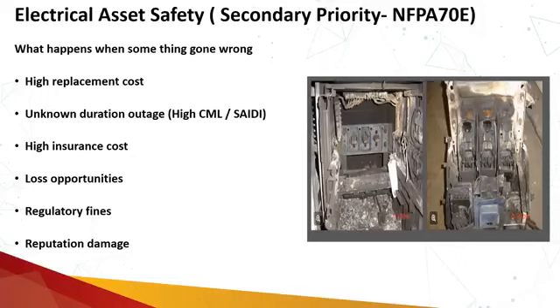But if I'm trying to bypass those known shutdown durations and trying to work on the equipment on the live system, and if any incident happens, some flashover happens, or some incident happens due to human error or any other reason, the asset will be completely damaged, or damaged to the extent that it will require complete replacement. That complete replacement might require 10 hours, 20 hours, or maybe more, because of non-availability of spares or of the equipment itself. So the chance you are taking when performing work on the live system is that you are moving from a known duration shutdown to an unknown duration outage as well.